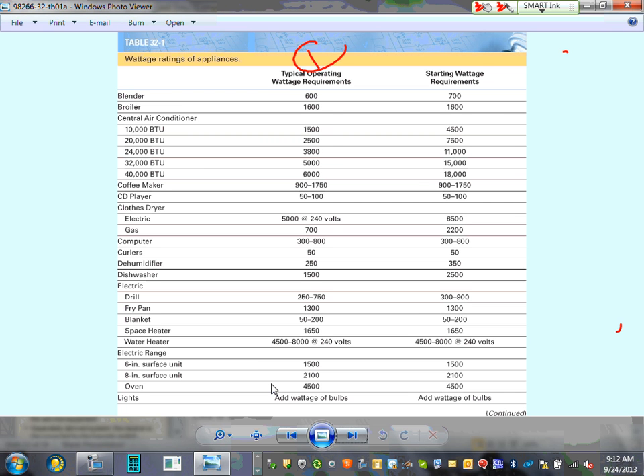Factor number one is the running load. They call it the running load. And factor number two is the starting load. If you guys understand this now, when I give you common software to size your generator for the two projects that are coming, it will be a piece of cake for you.